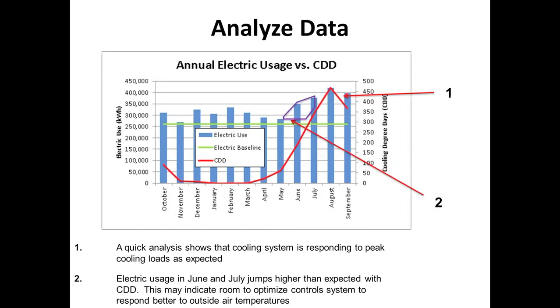Another way to really get more insight about your building and how well it responds to outside temperature is to plot those heating degree days and cooling degree days that we mentioned. For this building, on the cooling degree day side, you can plot cooling degree days against the actual electric usage for the building. We see that during the winter months, there are no cooling degree days, so most of the electric usage is going to be based on heat required for the building and also the base loads, plug loads, that electric miscellaneous category, lighting. What's interesting is that the building actually responds appropriately in August, which would be the hottest month for this year.